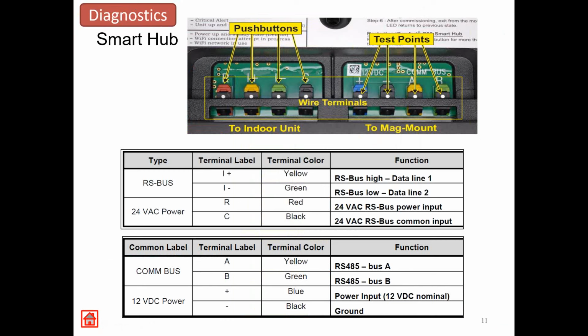Like we talked about earlier, we'll have R and C, which is your standard 24 volts, on the left side of this control. And then we have I plus and I minus, and that's your data communication wires between all the equipment. That's how it talks to each other back and forth. Just like a standard computer does, it sends a signal out, receives information, comes back and says, okay, I'm here, where are you at? That type of thing.